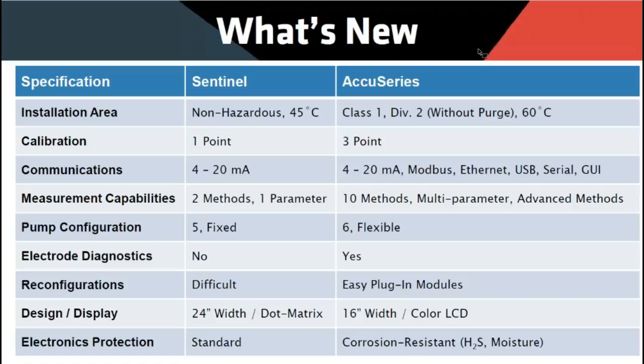So instead of the Sentinel being only suited for a general purpose area, only up to about 45 degrees C, we can now operate in Class 1 Div 2 as well as ATEX Zone 2 areas without a purge. And we can handle up to 60 degrees Celsius ambient temperature without a vortex cooler. So this would cover most applications and save a lot on cost. Calibration, instead of 1 point, we can now do up to 3 points, which increases our accuracy. Communications are greatly expanded to include Modbus, Ethernet, USB, serial connections, and we also have a great GUI.